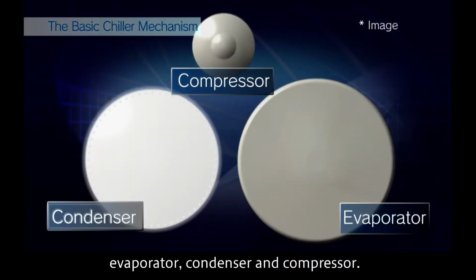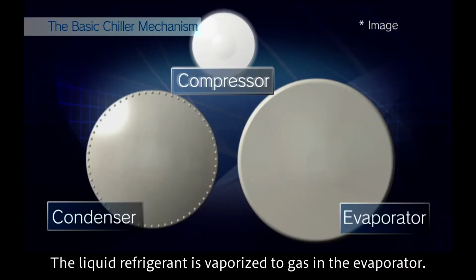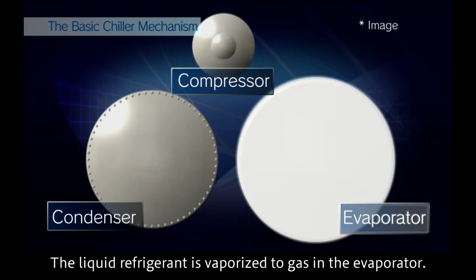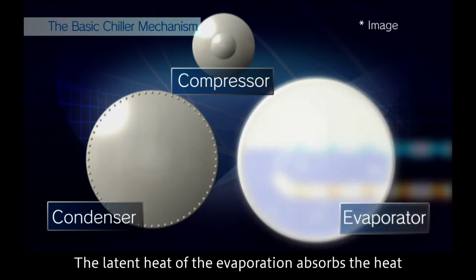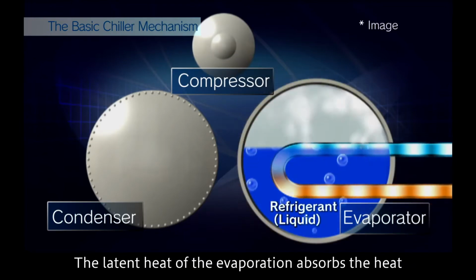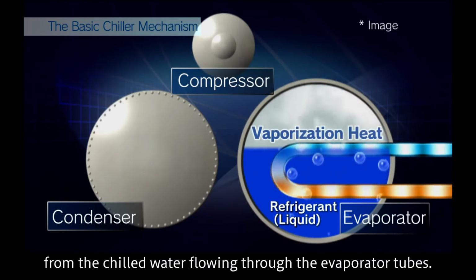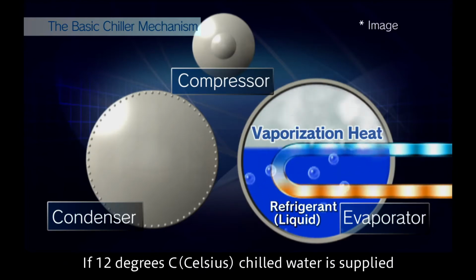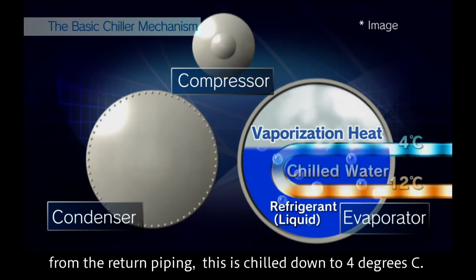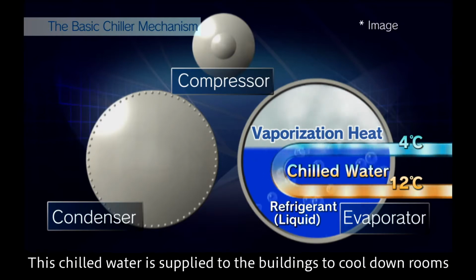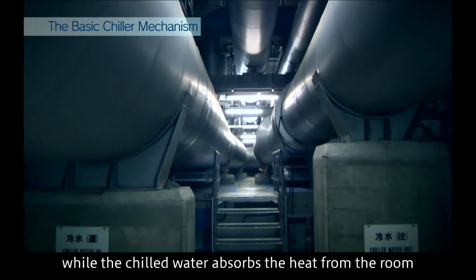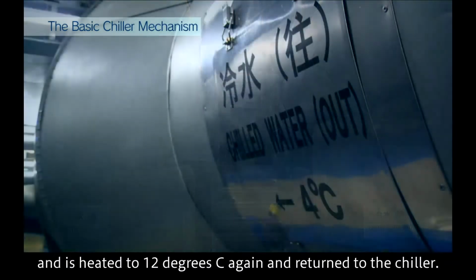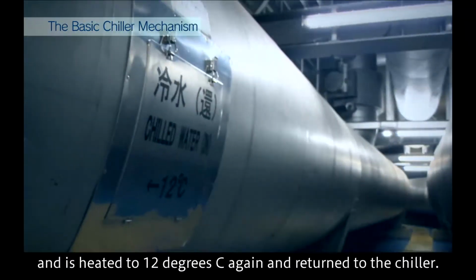The chiller is made up of 3 sections: evaporator, condenser, and compressor. The liquid refrigerant is vaporized to gas in the evaporator. The latent heat of the evaporation absorbs the heat from the chilled water flowing through the evaporator tubes. If 12 degrees Celsius chilled water is supplied from the return piping, this is chilled down to 4 degrees Celsius. This chilled water is supplied to the buildings to cool down rooms, while the chilled water absorbs the heat from the room and is heated to 12 degrees Celsius again and returned to the chiller.